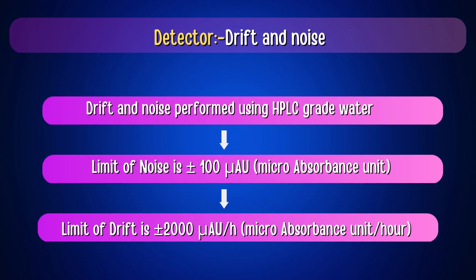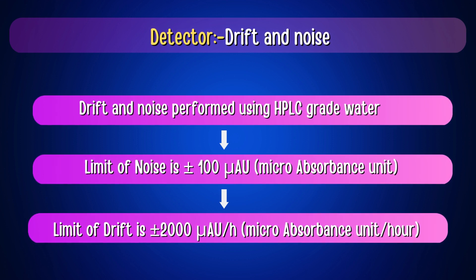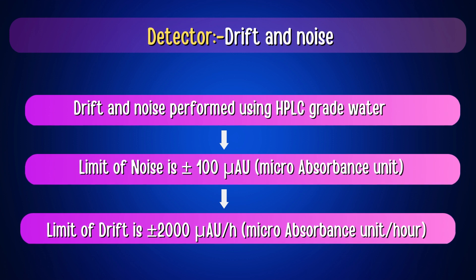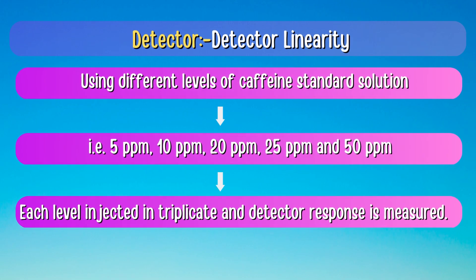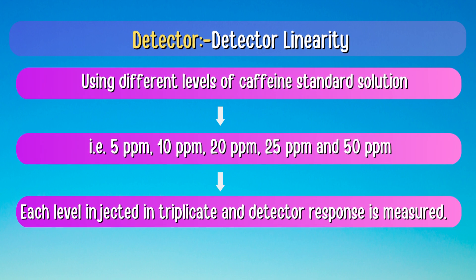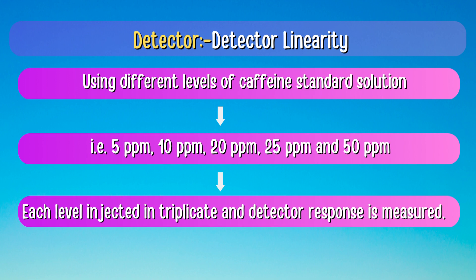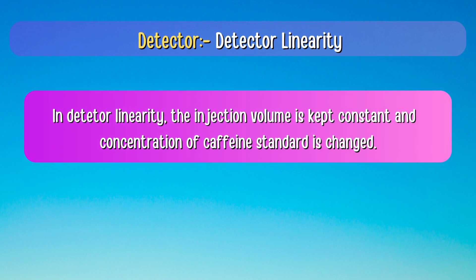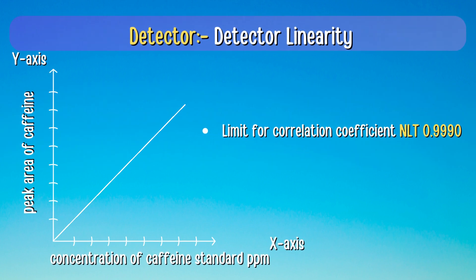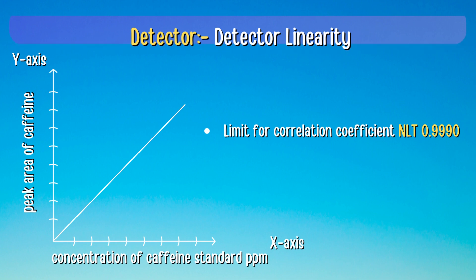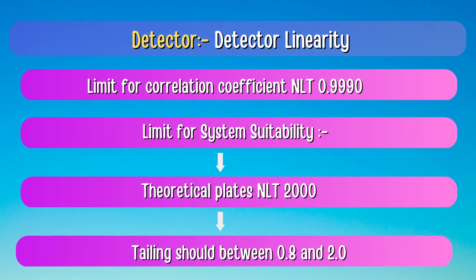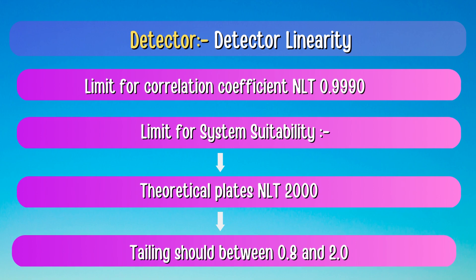For Drift and Noise, the test is performed using HPLC grade water. The limit for noise is ±100 µAU and the limit for drift is ±2000 µAU per hour. For Detector Linearity, different levels of caffeine standard solution are used: 5 ppm, 10 ppm, 20 ppm, 25 ppm, and 50 ppm. Each level is injected in triplicate and detector response is measured. The injection volume is kept constant while the concentration of caffeine standard is changed. A linearity graph is plotted with concentration on the x-axis against average peak area on the y-axis, and the correlation coefficient and system suitability are checked. The limit for correlation coefficient should not be less than 0.999. For system suitability, theoretical plates should be not less than 2000 and tailing factor should be between 0.8 and 2.0.